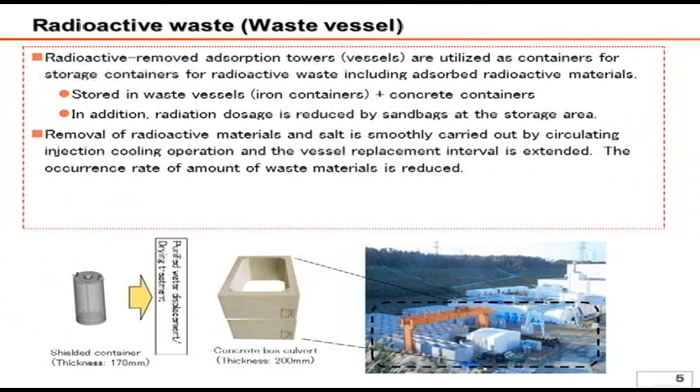This absorption vessel contains zeolite inside which absorbs cesium, so the apparatus itself becomes radioactive waste. Accordingly, the apparatus has to be properly stored while its surface radiation level is under close surveillance. We plan to store the apparatus, which is a shielded iron container with a 170 millimeter thickness, in a square-shaped concrete box called a box culvert.